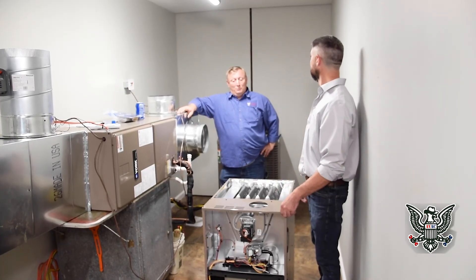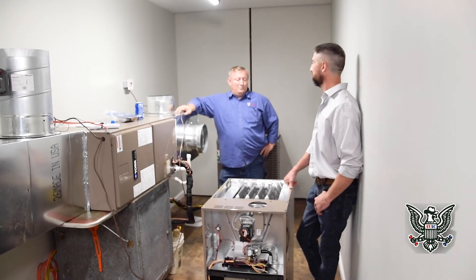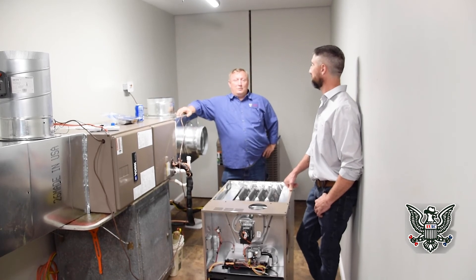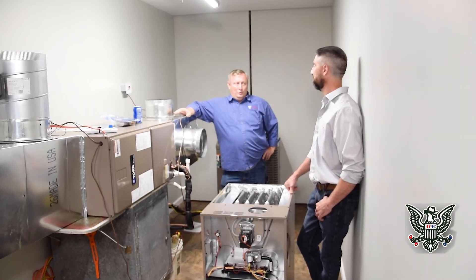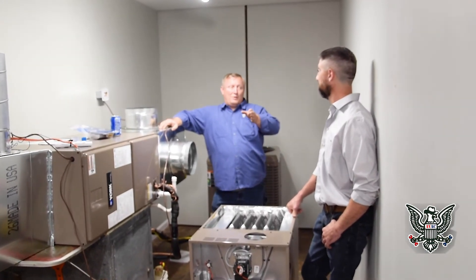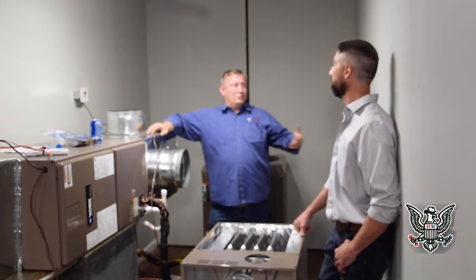That's important. Some more things to look at during an inspection: is the flame straight? It should be blowing directly down the tube. If it's flickering or moving left and right a lot, it's a sign of other things that need to be inspected.